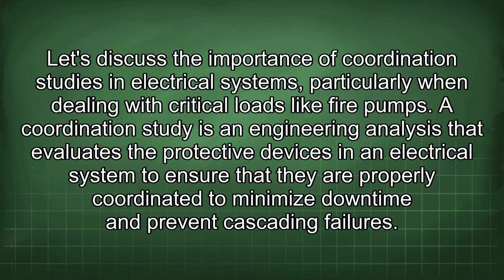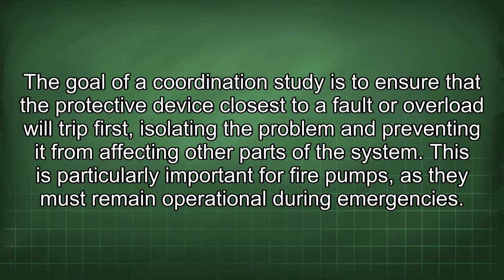Let's discuss the importance of coordination studies in electrical systems, particularly when dealing with critical loads like fire pumps. A coordination study is an engineering analysis that evaluates the protective devices in an electrical system to ensure that they are properly coordinated to minimize downtime and prevent cascading failures. The goal of a coordination study is to ensure that the protective device closest to a fault or overload will trip first, isolating the problem and preventing it from affecting other parts of the system. This is particularly important for fire pumps, as they must remain operational during emergencies.